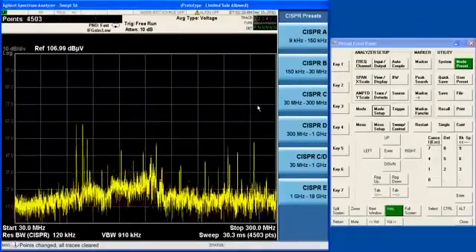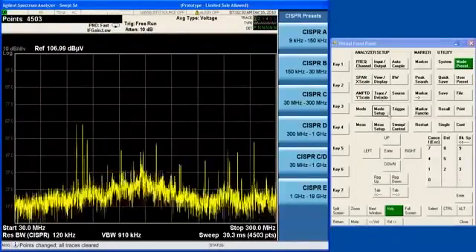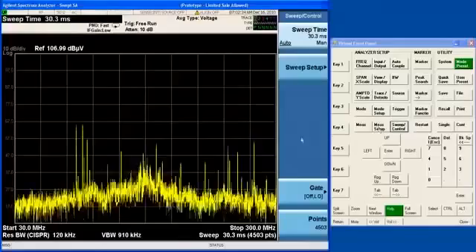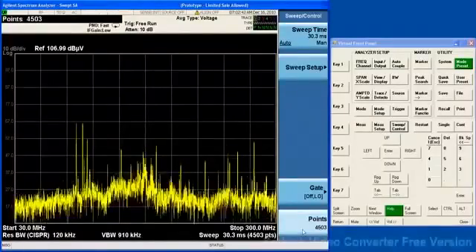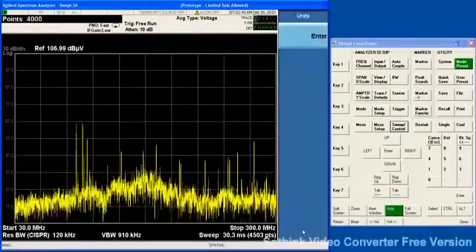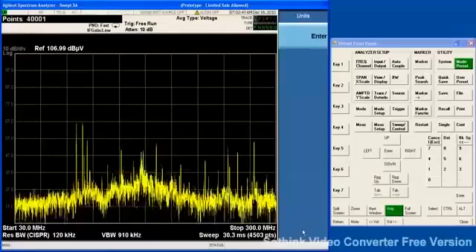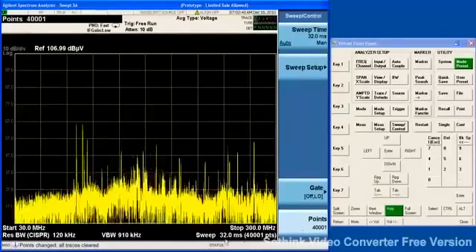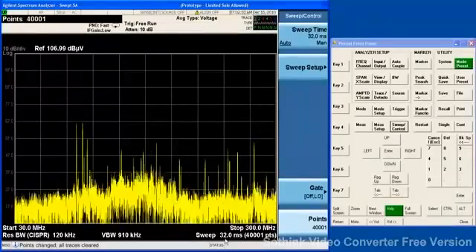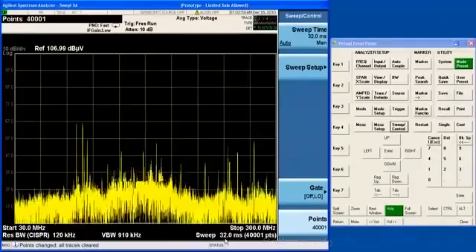With the X-Series, you can set up to 40,000 sweep points, allowing you to resolve very narrow signal spacings, even in a wideband sweep. And notice that the sweep time is impacted very little by changing the number of points.